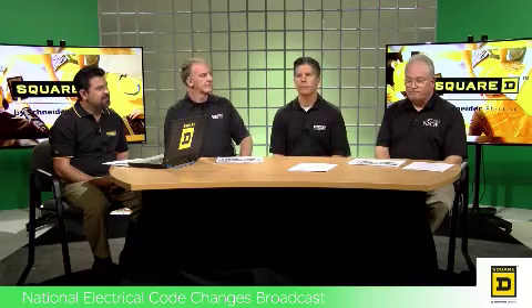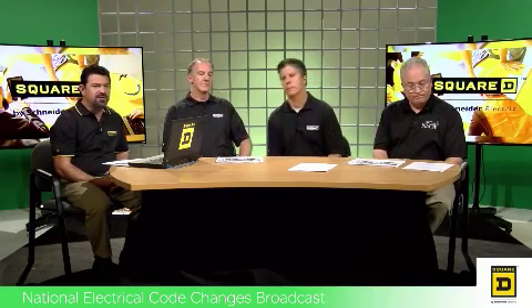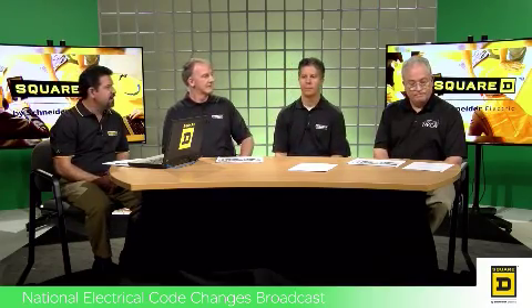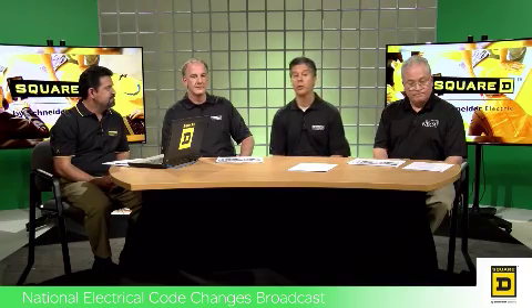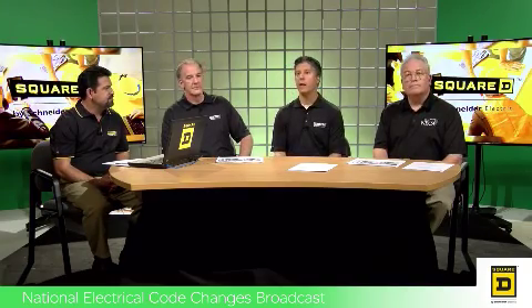Thanks, Mike. Appreciate it. Chad, can you give us some information on the changes to 210.8? Yeah, glad to do so, Phil. 210.8 gives GFCI protection for other than dwelling unit locations. And we have an expansion here for single-phase receptacles, moving from 20 amperes to 30 amperes to 50 amperes, and three-phase receptacles moving to 100 amperes.